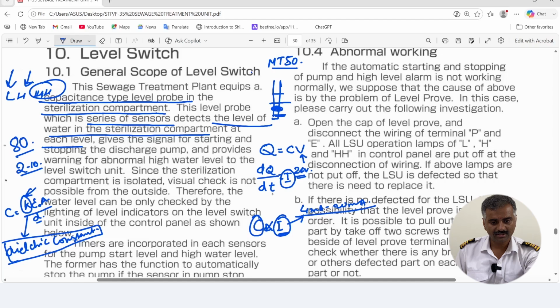As water comes in, the dielectric changes. Water has a higher dielectric. The current flow and capacitance change. The flow of current changes through the circuit. That's how the level sensor identifies that there is now a low level. And as the level rises to the high level, again at the next level your dielectric changes, so your current flow changes, and your level probe works in such a manner.